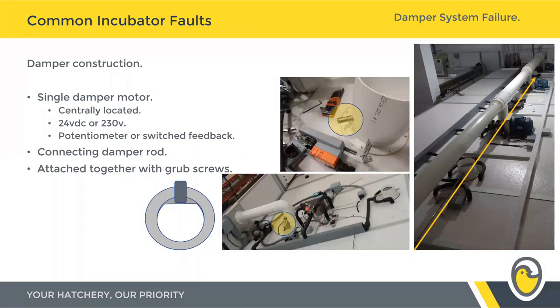If at some point that grub screw comes loose, your damper motor will activate and turn, but it won't continue that motion all the way down the machine. What you can find is that three of your dampers work absolutely fine and then three of them may not.